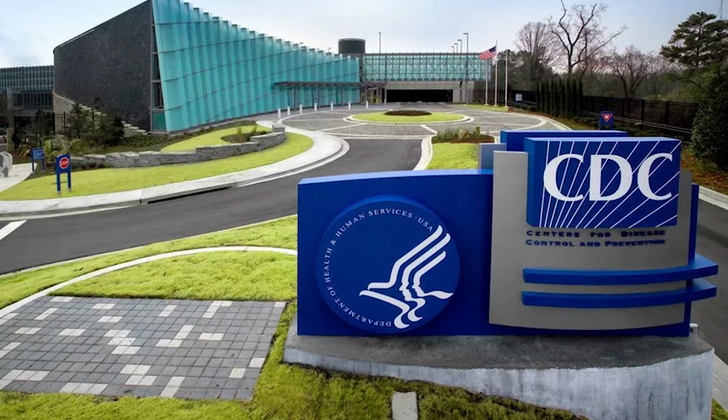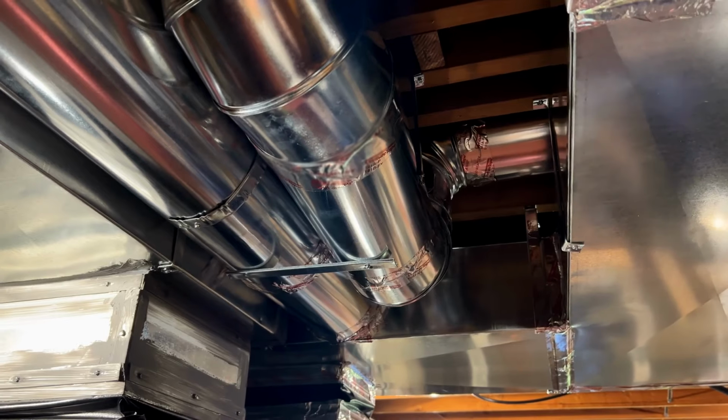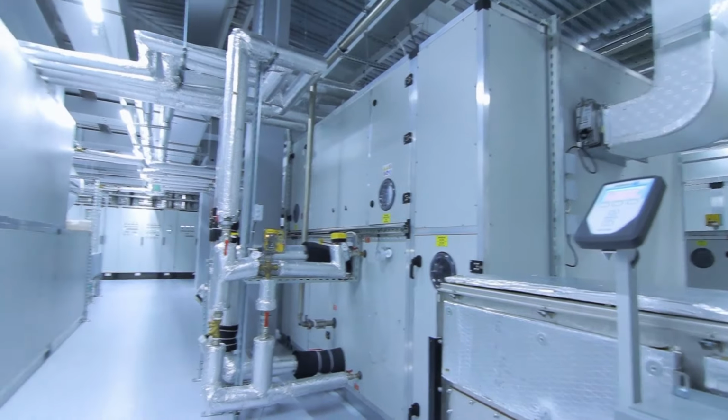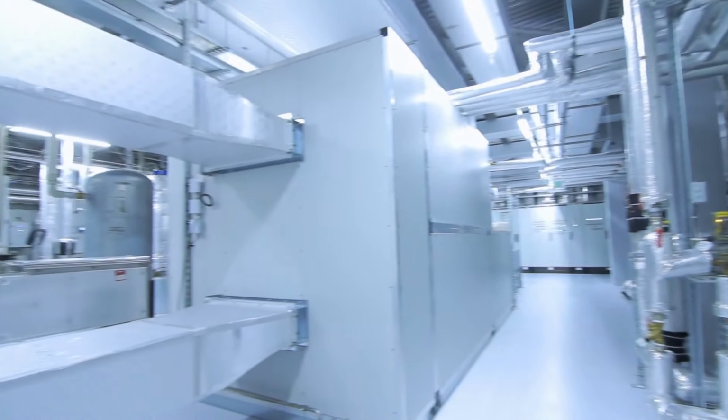So a good building is typically 3. The CDC is recommending a minimum of 5. And ASHRAE, depending upon the application, uses a more complex equation that can go significantly higher. So places like hospitals, up to 15 air changes an hour. That's really, really expensive to do, considering how many buildings there are. It's the largest asset class in the world, so the energy implications are huge.